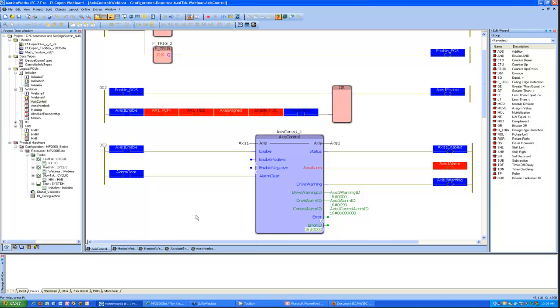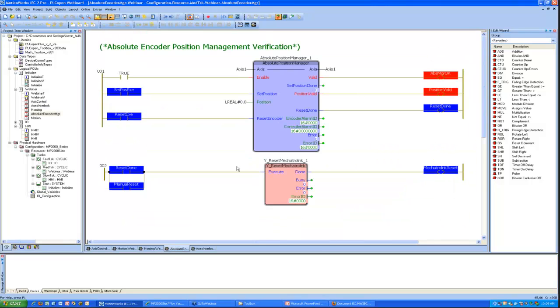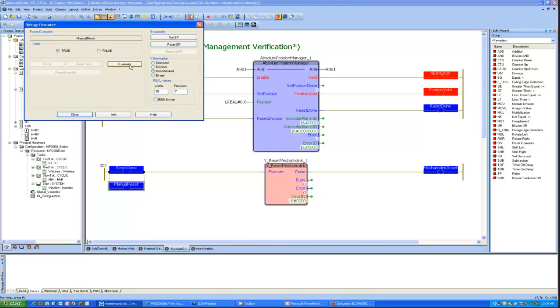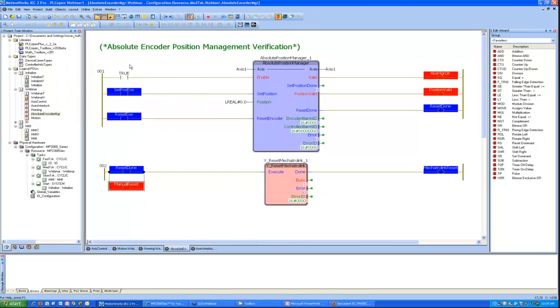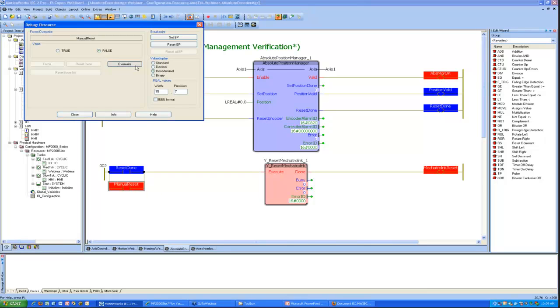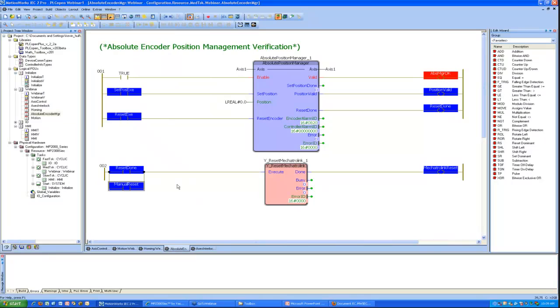Okay, so this alarm is not clearable by simply a casual alarm clear. But it requires power cycle according to the documentation in the servo pack manual. Well, in addition to that, we can actually clear that via software by resetting Mechatrolink, because that causes a soft reboot of the servo packs. So if I reset the Mechatrolink, the AC9 alarm will disappear.